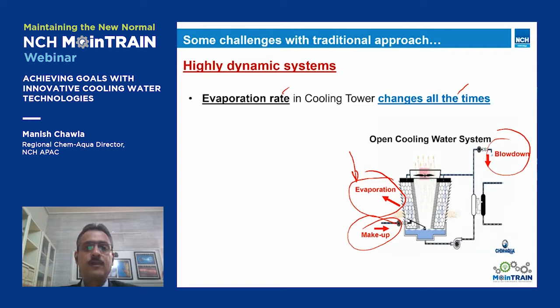So it will depend on the ambient weather conditions, the relative humidity, the diurnal temperature. It will depend on your plant load. Like in COVID-19 time, sometimes you operate 50%, sometimes you operate 100%. Evaporation rate will keep on changing, and we cannot control it. So when the evaporation rate keeps on changing, we need to be controlling the blowdown.